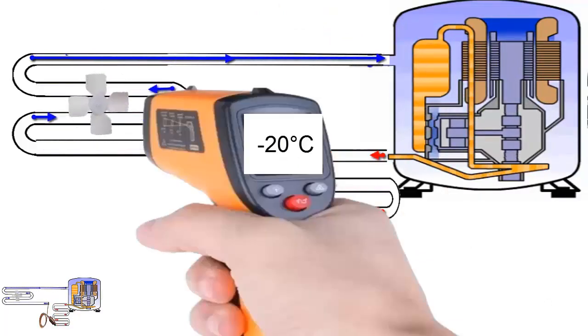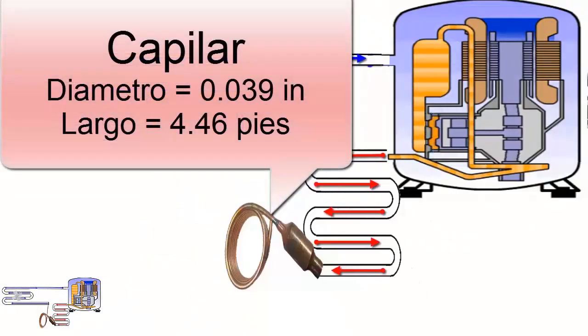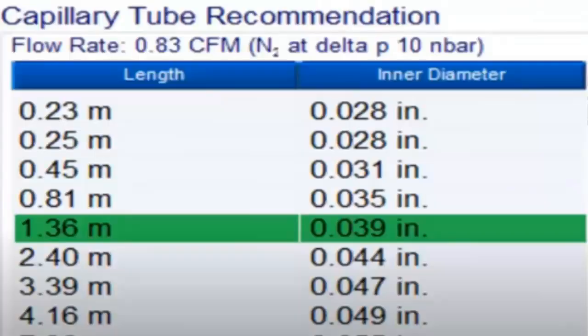For a temperature of minus 20 degrees Celsius, a capillary tube with a diameter of 0.039 inches and a length of 4.46 feet, equivalent to 1.36 meters, is recommended. On the screen, we are showing other alternative measures for the capillary tube.